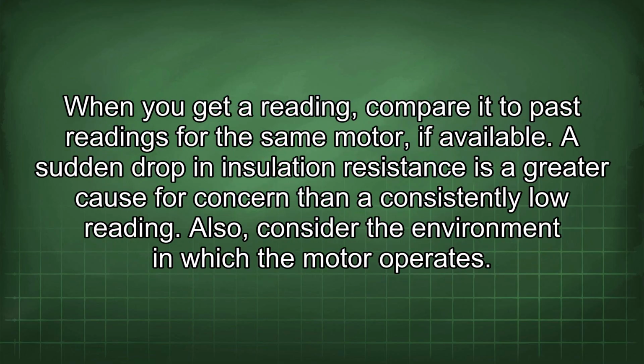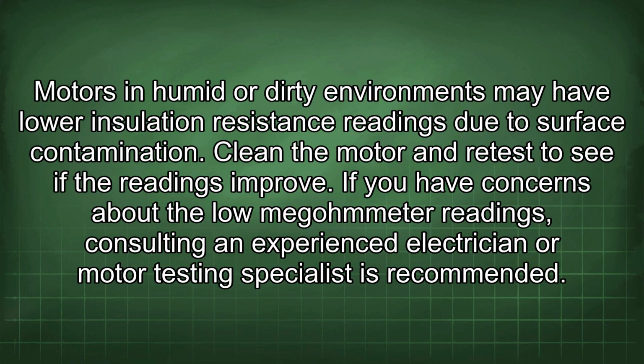However, remember that this is just a general guideline, and other factors may still affect the health of the motor's insulation. When you get a reading, compare it to past readings for the same motor, if available. A sudden drop in insulation resistance is a greater cause for concern than a consistently low reading. Also, consider the environment in which the motor operates. Motors in humid or dirty environments may have lower insulation resistance readings due to surface contamination. Clean the motor and retest to see if the readings improve.